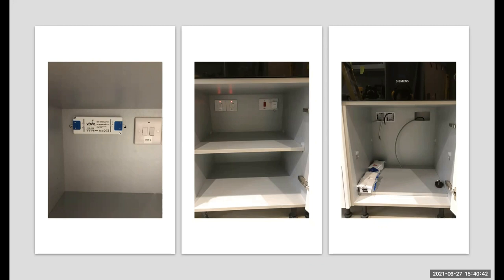I had a guy that kept complaining, and it wasn't my job, I have to say. I was doing the loft conversion, and this was in the kitchen that was wired by others. And he kept saying that he had a problem with his oven. And it turned out that they'd rammed the cupboard so full of stuff that the cooker isolator was being rocked partially on and off. And it was sparking and arcing in the back of the cupboard, which obviously, again, generates heat, which could cause a fire.